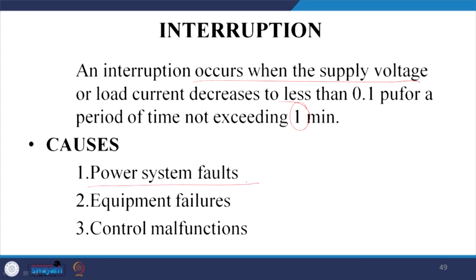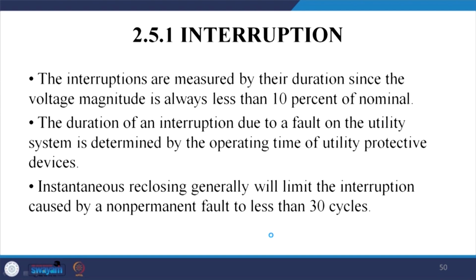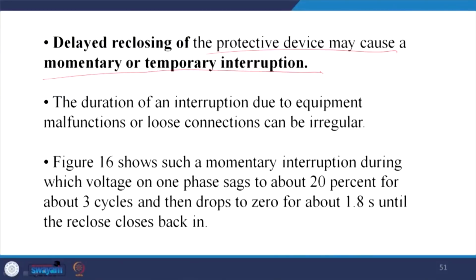Causes: power system faults, equipment failures and control malfunctions. An interruption can be measured by its duration, since the voltage magnitude is always less than 10% of the nominal voltage value. The duration of an interruption due to a fault on the utility system is determined by the operating time of the utility protecting devices. Instantaneous reclosing will generally limit the interruption caused by a non-permanent fault to less than 30 cycles. One cycle is 20 milliseconds. So, you should reconnect within 30 cycles, otherwise it is considered an interruption. A delay in reclosing the protecting device may cause a momentary or temporary interruption.